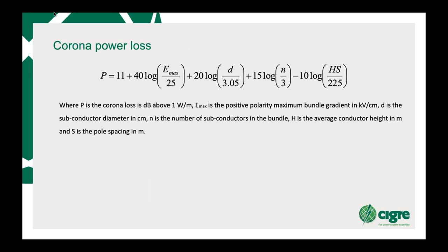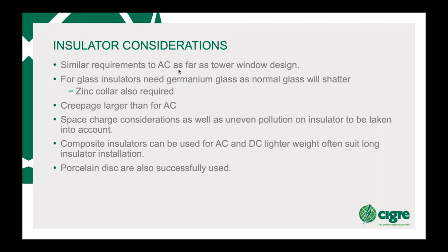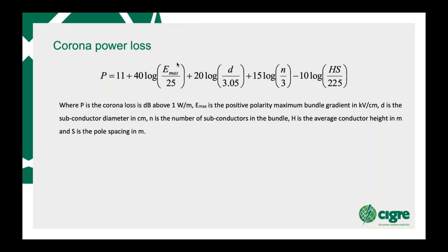Now, looking at the corona loss, P is the corona loss, in dB above 1 watt per meter. Emax is the positive polarity maximum bundle gradient, D is the subconductor diameter in centimeters, and N is the number of subconductors. And what we're finding here is that it's almost exactly the same as the AC case. So to reduce the corona, you need bundles with a large number of subconductors in the particular bundle. The bigger the diameter of these subconductors, the lower the corona loss.